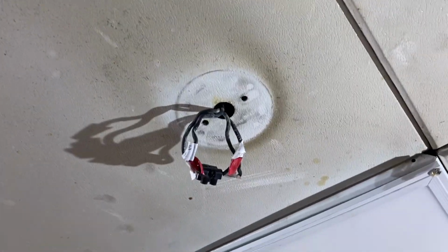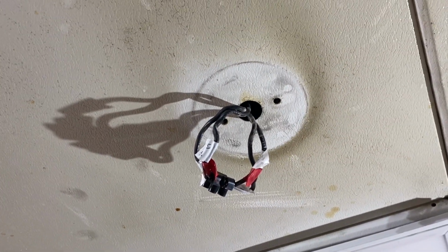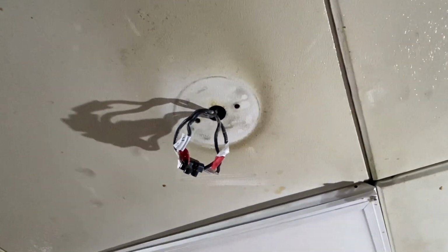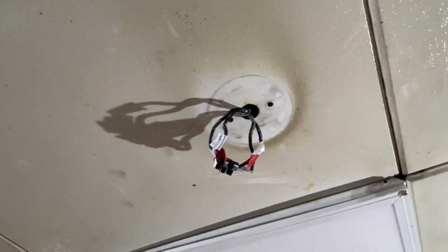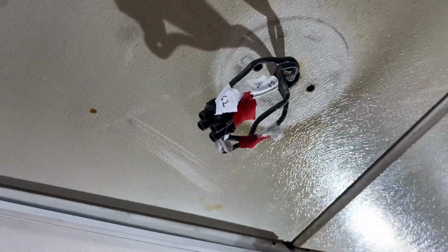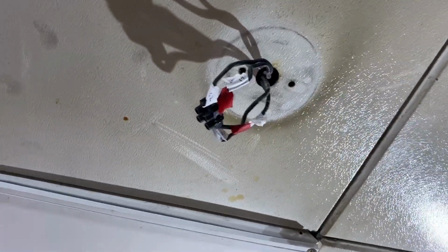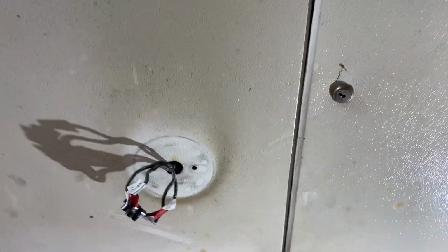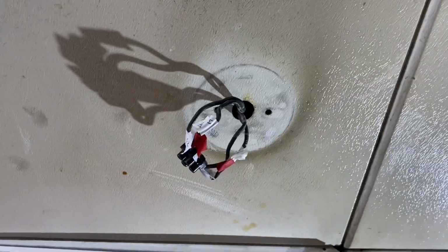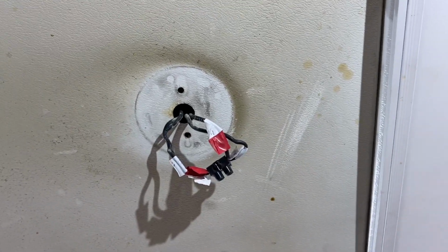So, as a temporary fix, I've disconnected the detector and put the connector blocks on it, just to bypass that faulty detector, because it's showing a fire when it's really not, considering it's water damage. As always, remember to label them up, what's in and what's out. Let the customer know that this area won't be detected for the time being until the works are done here. Bypass it by using connector blocks to have a fault-free panel as a temporary fix until all the works are finished in here.